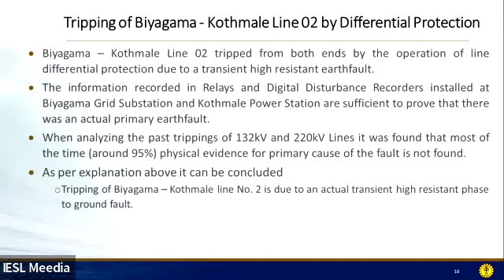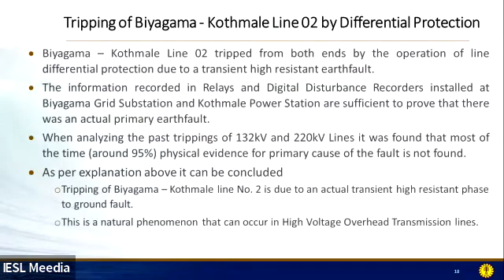As per the explanation given above, it can be concluded that the tripping of Biyagama-Kothmale line 2 is due to an actual transient high resistance phase to ground fault. This is a natural phenomenon that can occur in high voltage overhead transmission lines. Hence, the possibility of sabotage can be ruled out. That's our final remark on this particular tripping of this particular line.